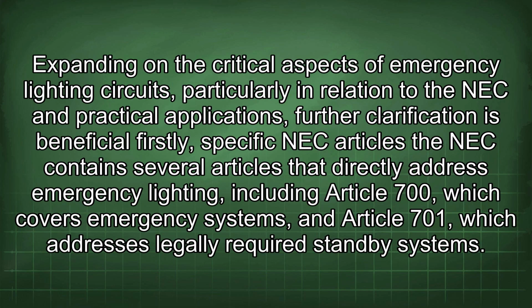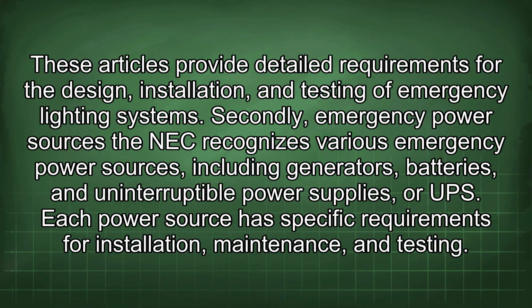Expanding on the critical aspects of emergency lighting circuits, particularly in relation to the NEC and practical applications, further clarification is beneficial. Firstly, specific NEC articles. The NEC contains several articles that directly address emergency lighting, including Article 700, which covers emergency systems, and Article 701, which addresses legally required standby systems. These articles provide detailed requirements for the design, installation, and testing of emergency lighting systems.